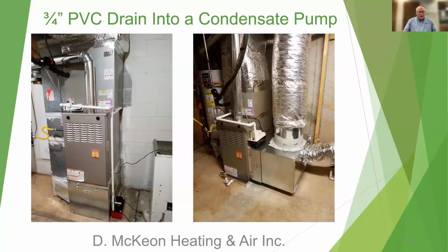Two more examples of condensate drains going to pumps. Notice the one on the left, just directly off the evaporator coil, there's a 3/4 inch union. It's hard to see, but it's right there above the black knob on the left of the furnace. What that does is enable you to unscrew that, clean the pipe out, and then put it back together. So it's an easy way to clean your pipes every year right there on the condensate drain. The one on the right is just another typical example. It does have an emergency drain pan under it also.